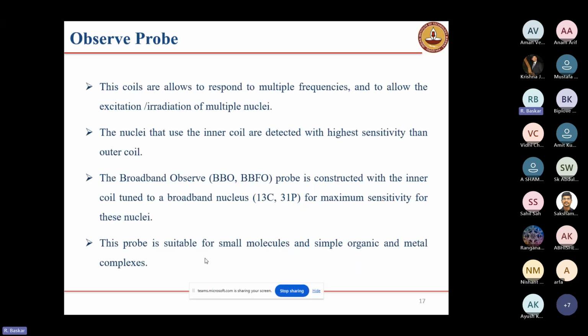These coils respond to multiple frequencies and allow the excitation or irradiation of multiple nuclei. The nuclei that use the inner coil are detected with higher sensitivity than the outer coil, because the inner coil is close to your sample. In the broadband observe probe, the inner coil is tuned for the broadband X nucleus, other than proton. It gives the maximum sensitivity for nuclei other than proton, for example C13 or P31. So these probes are suitable for people working in organic chemistry, small molecules, and regular experiments.